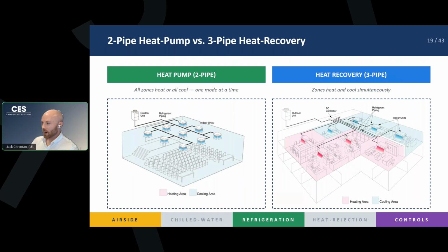Our heat recovery is going to allow the heat to be moved from hot zones to cold zones without using energy, putting in the work at our compressor. It's free cooling and free heating, and makes these VRF systems extremely energy efficient when you're using heat recovery. The caveat: you need that 3rd pipe. It's the only way to get that heat transfer across zones.